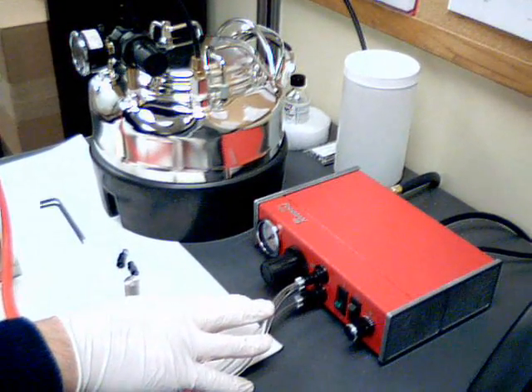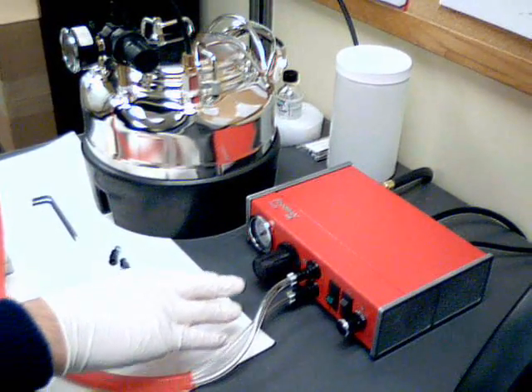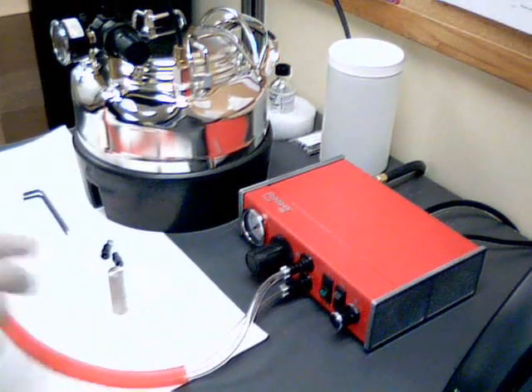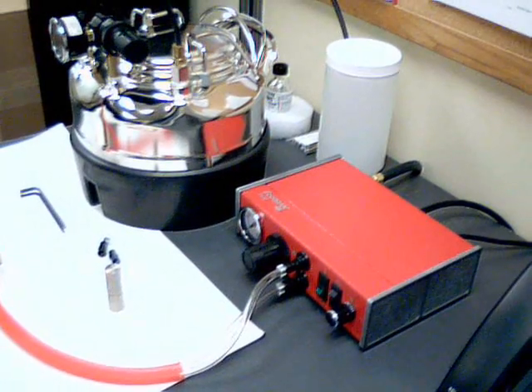We have an air pulse unit here, 7400. The air pressure here has been preset to 70 psi, which is what this valve or filling station calls for.